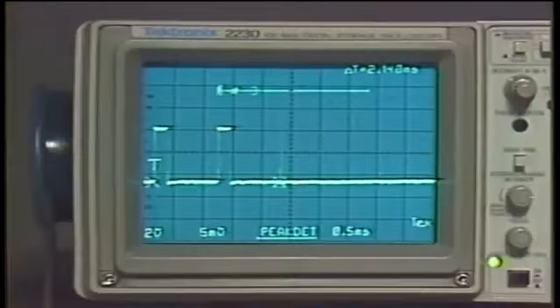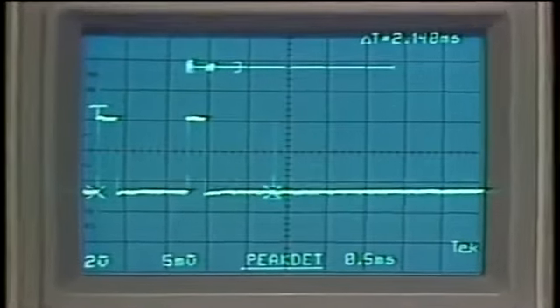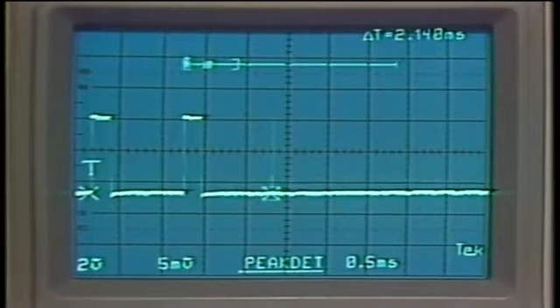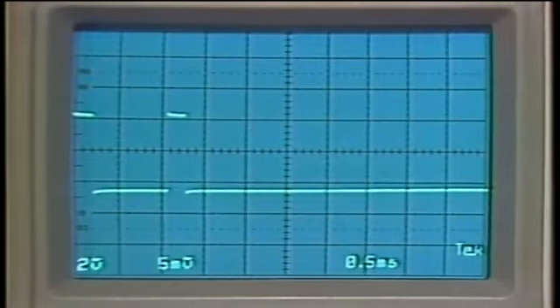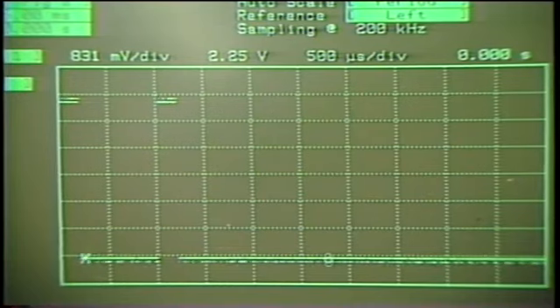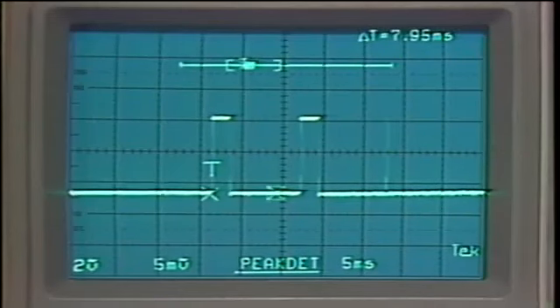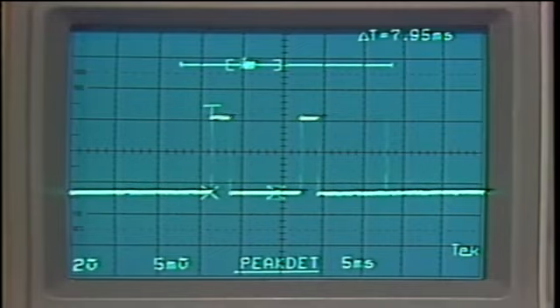Do you need to find fast glitches in waveforms? These are difficult to detect on analog scopes, especially if you don't know they're there. And CRT storage scopes or conventional digital storage scopes don't display them either. All 3 of these new DSOs have peak detection, displaying any spike wider than 100 nanoseconds, regardless of the sweep speed selected. This is a timing error splinter, only about 300 nanoseconds wide.